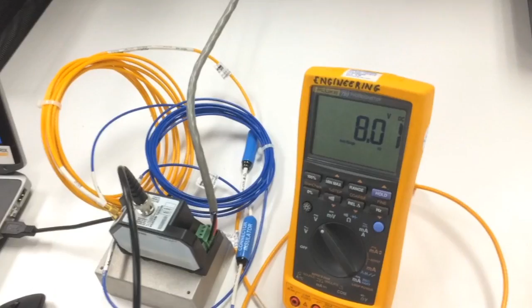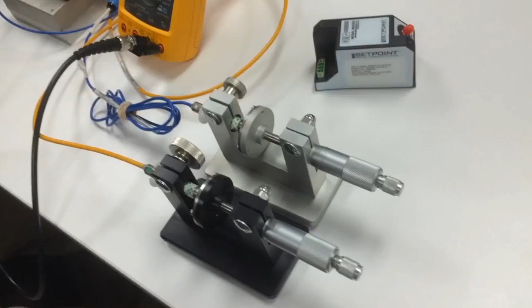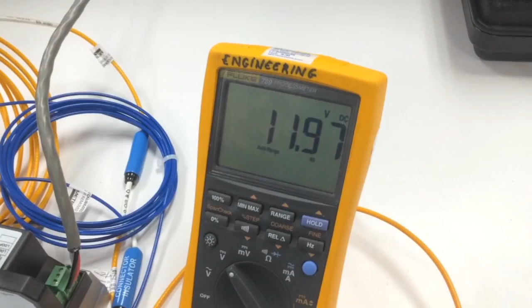Then let's take another measurement at 60 mils. If you look at the multimeter here, you'll see that it's approximately 12 volts. So if you subtract 8 from 12, you get 4 volts, which corresponds to the 20 mil difference between the probe and the tip that I've just moved it.